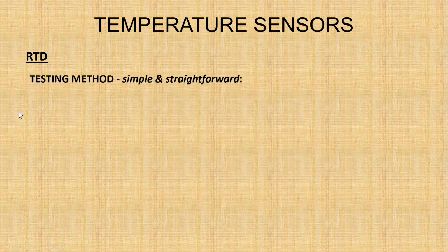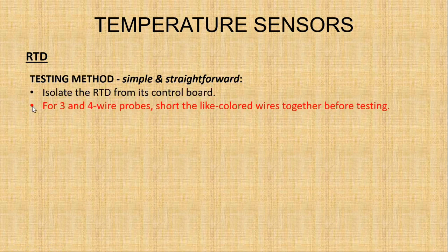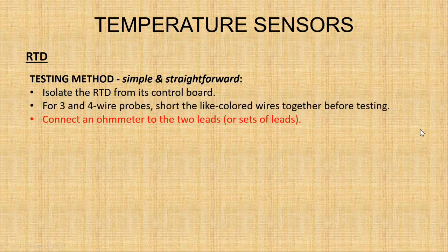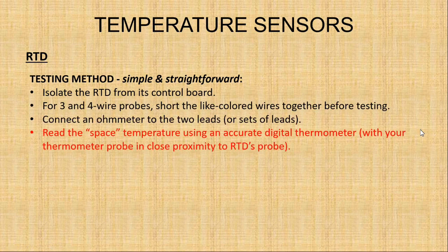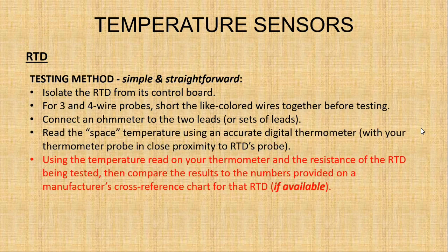Testing methods for RTDs is simple and straightforward. You isolate the RTD from its control board. For 3 or 4 wire probes, short the like-colored wires together before testing. Connect an ohmmeter to the 2 leads or sets of leads. Read the space or heating, cooling, and medium temperature using an accurate digital thermometer. Do this with your thermometer probe in close proximity to the RTD's probe. Using the temperature read on your thermometer and the resistance of the RTD being tested, compare the results to the numbers provided on a manufacturer's cross-reference chart for that RTD, if available.